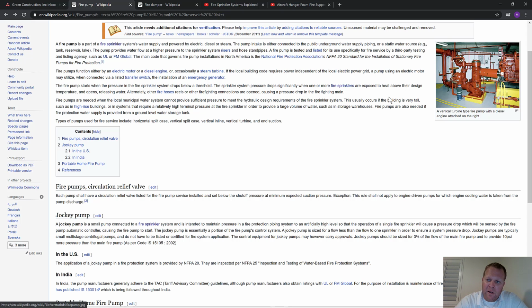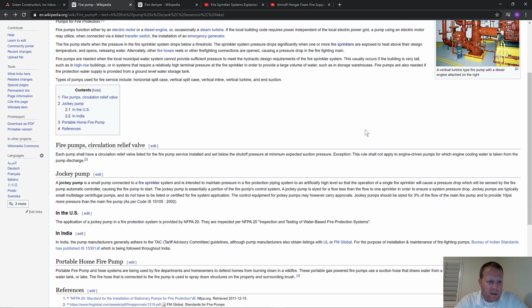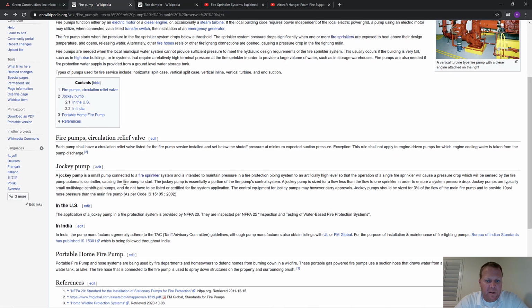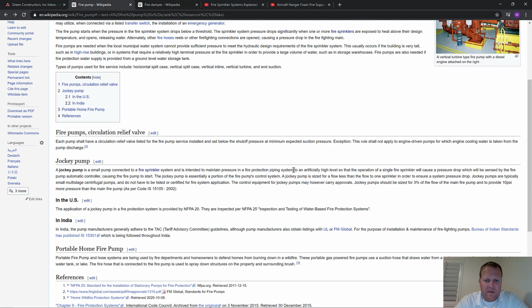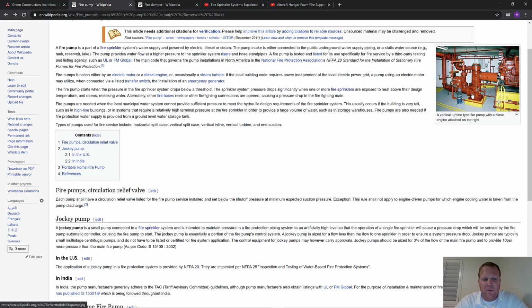But usually you have the city's piping either coming here, or you have a reservoir tank on the outside of the building that's also feeding water to this. So it could be a couple of different scenarios with the fire pump. They also have something called a jockey pump, and the jockey pump is just keeping the pressure inside the pipe. So the little jockey pump is there. Let me explain a little bit here. The fire pump is usually running off of a pressure drop, monitoring the pressure inside the pipe. And why would the pressure drop inside the pipe? Well, the pressure would drop if a sprinkler head broke, or the little bulb went off because it heated up in a fire, and the water in the pipe would go out that orifice and try to provide suppression for the space.